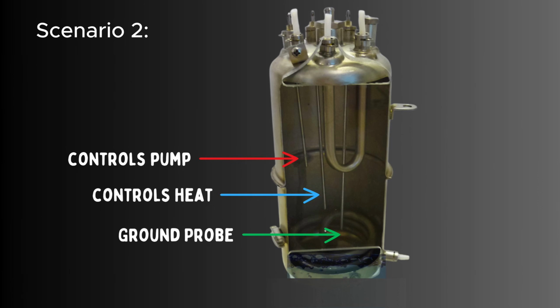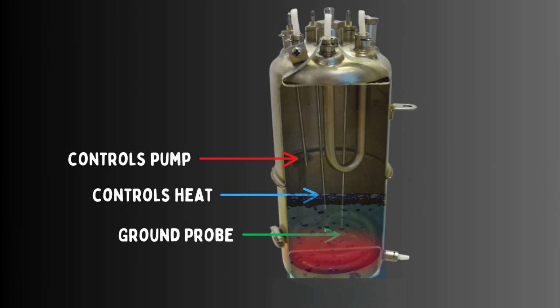Number 2, the boiler only half fills. You can hear it boiling, but the steam doesn't work. This can happen if steam gets into the red probe while it's still filling up. And because the blue probe is submerged, it's going to turn on the heat. But because there's only a little bit of water in there, it's going to get hot very quickly. So quick in fact that the little temperature sensor on top of the boiler is not going to have time to read how hot it's getting, and it's going to continue to ask for more heat. And eventually it's either going to trip the thermostat on the side or it's going to blow the thermal fuse.